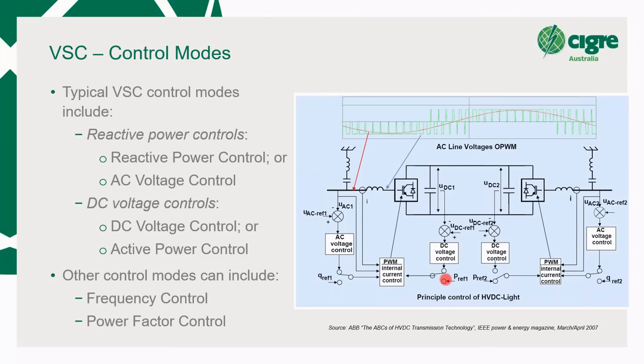So you can see here, one converter is in DC voltage control, so it's just holding the DC voltage. The other converter is in P control, and that's the operator typing in an active power level that they want the converter to transmit. And that goes into the PWM, and that causes the AC waveform that's being built by the converter to determine what angle. It's measuring what's on the AC network. It's saying, right, I need to build an AC voltage waveform of this particular angle.